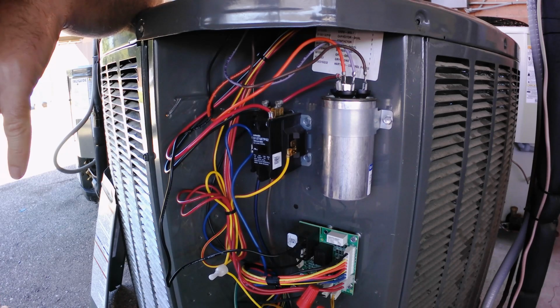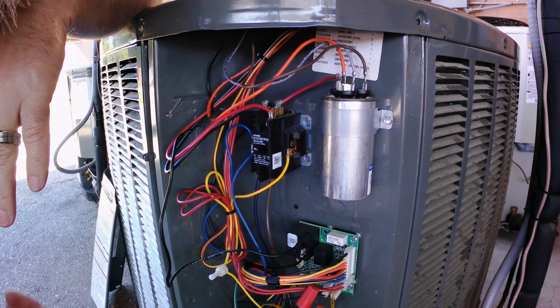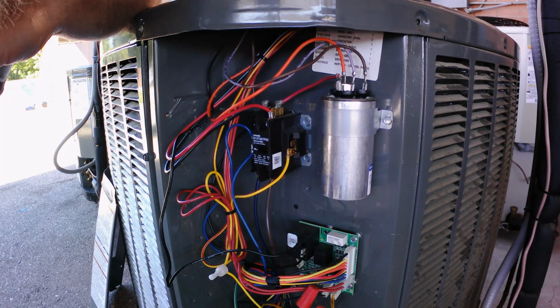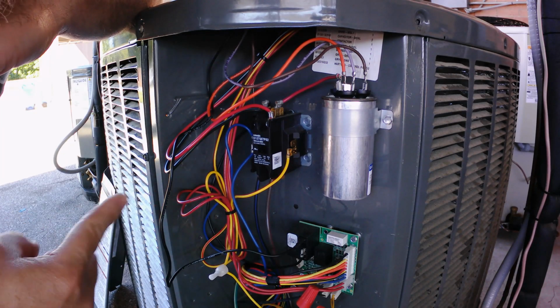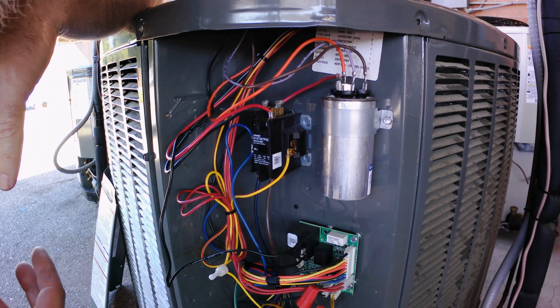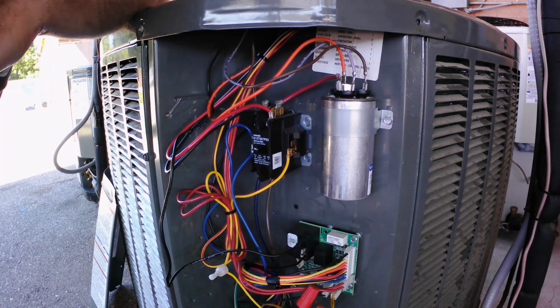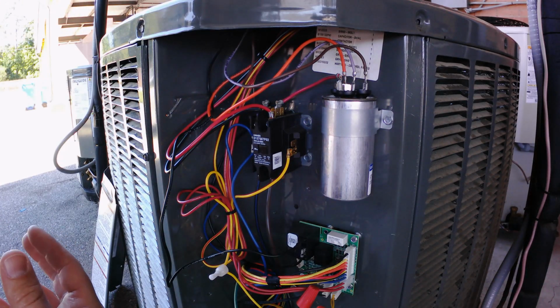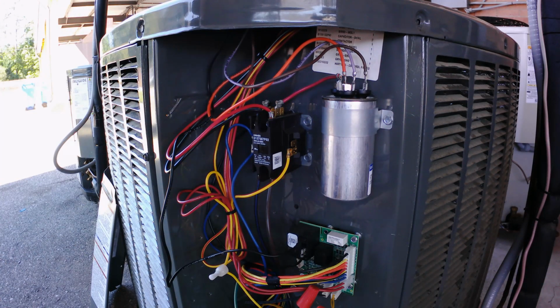If we were going to guess at everything, we wouldn't buy all these tools. So the tools are what you need to master. You need to get the basics down in your head, and don't let something as simple as a bad relay or a bad contactor cause you to misdiagnose and then possibly get looked at funny by a customer when you tell them, hey, this is a bad $500 motor or whatever, and it's really just a simple $100 contactor. So troubleshoot it as best you can, do it right. If you have any questions, then let me know. Until next time.